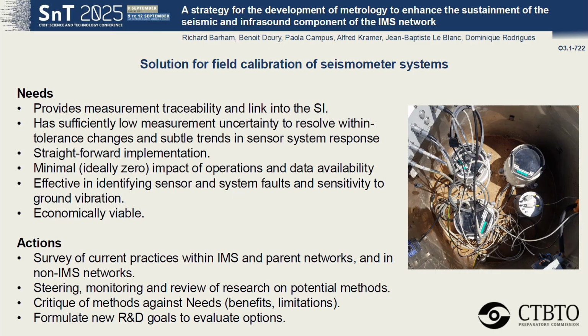And this is something that spans all technologies. But here on the slide, we're looking particularly at seismometer systems. And the needs here are that we need to have traceability, measurement traceability, so it links with the SI. We need to have low enough measurement uncertainties so that any changes can be resolved and not hidden by the uncertainty of the calibration methods.